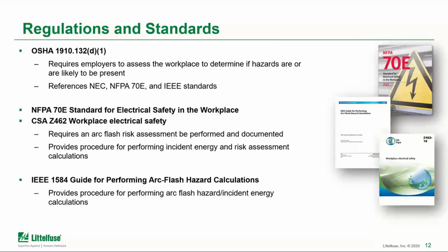So NFPA 70E, the standard for electrical safety in the workplace, and the harmonized version of that in Canada, CSA Z462 workplace electrical safety, talk about how to provide electrical safety policies and procedures in the workplace. Those standards also require an arc flash risk assessment to be performed and documented. And there are procedures outlined in those standards that go through how to do risk assessments for arc flash and for shock protection, and that also links back with IEEE 1584.